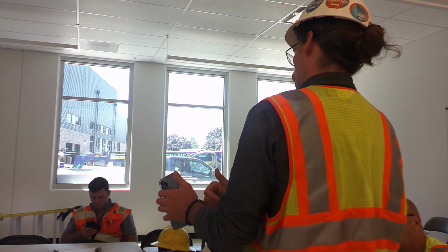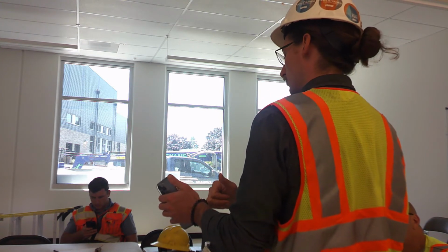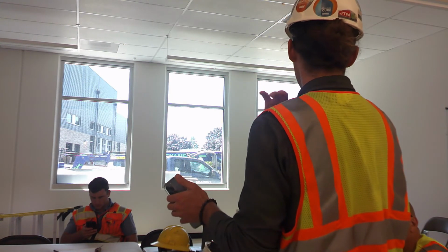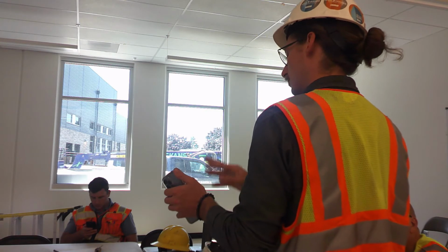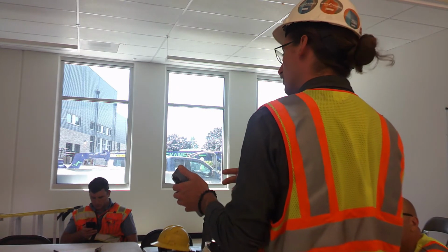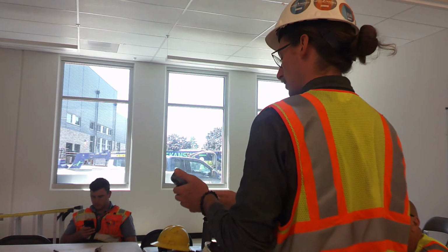At the bottom, you'll see what group they're in. So that's another useful thing. This relay is in group 3, so that's going to correspond to how the buttons are programmed. So that relay will listen to any buttons that are programmed to group 3, any sensors that are programmed to group 3, and same with the photocells.